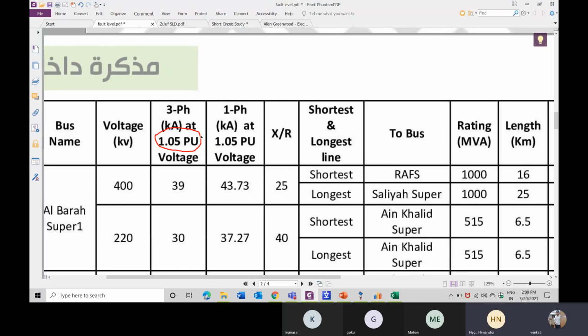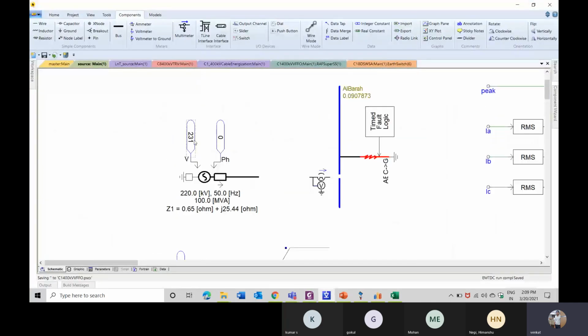To make this happen, I have taken a 5% margin for the particular 220 kV. If we take a 5% margin increase, just increase the 220 kV to 1.05 per unit. What happens is it will come to 231. That is what I have done here, to make that scenario happen I have kept it as 231.